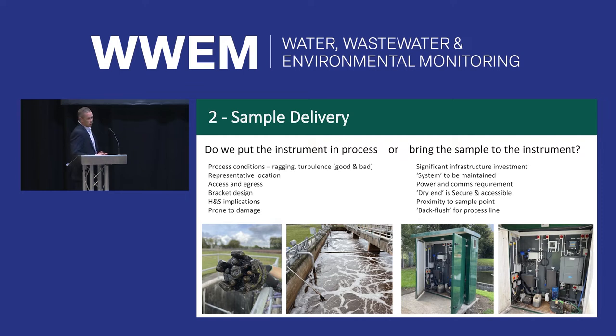On the left, I went to site with Ben, who was in the audience a couple of weeks ago, and we pulled a sonde-type approach with an ion selective probe - that's the image on the left. Our biggest concern with that type of installation is keeping it clean - do we put an air blast on it, water, chemical clean, wipers? Different manufacturers I've seen over the last couple of days have various different approaches.